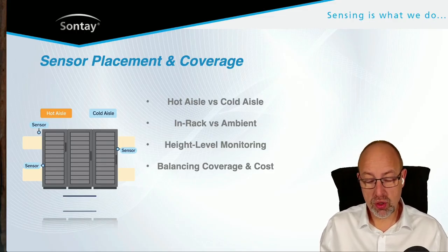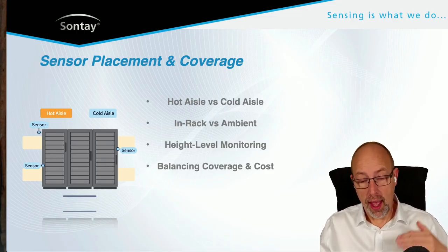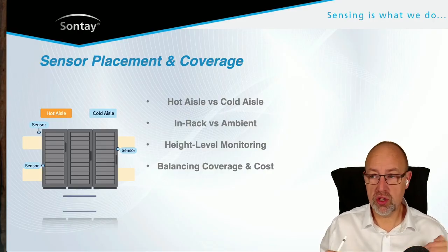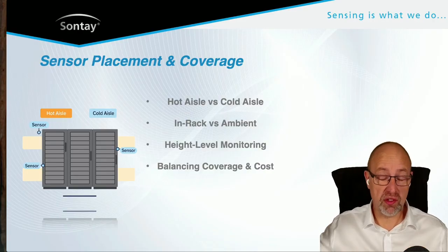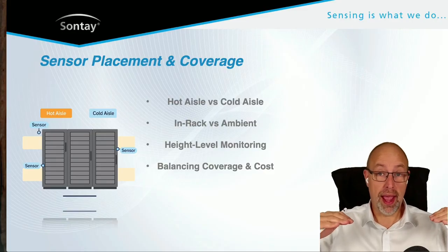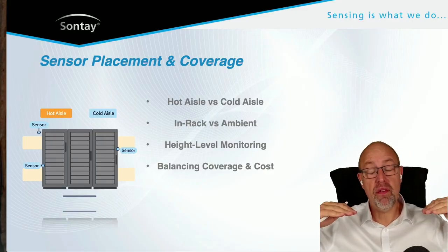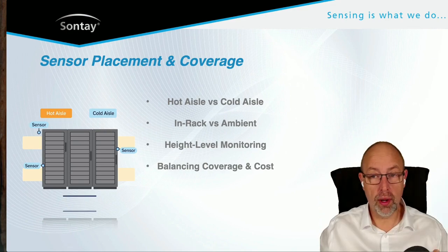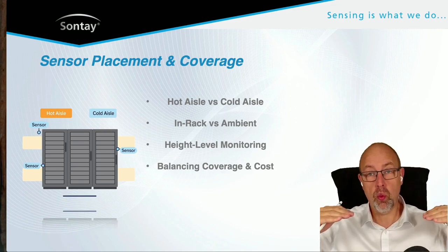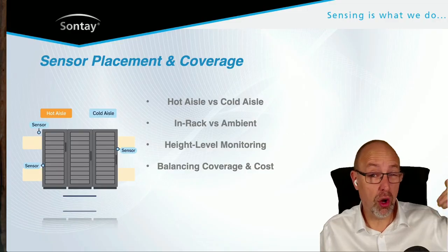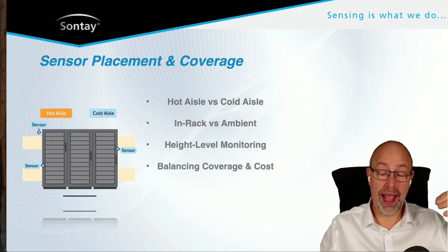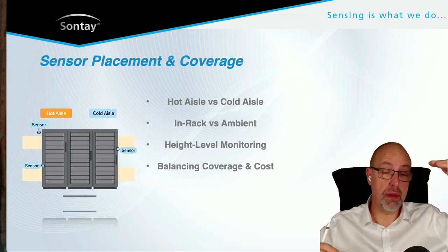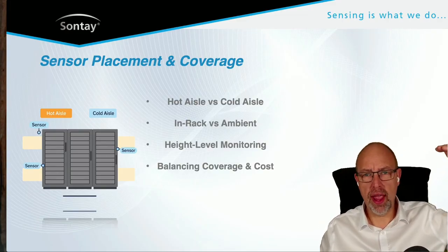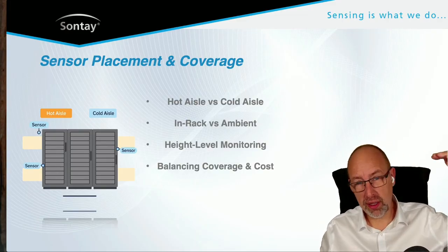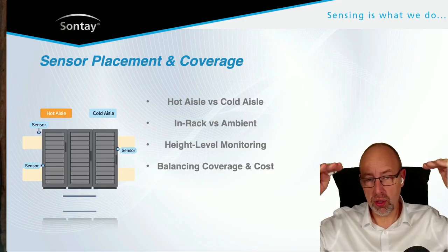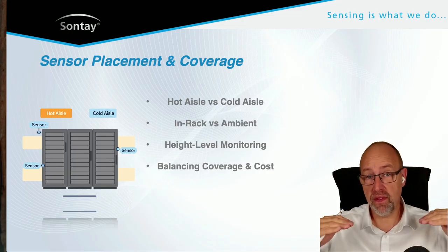Another thing which is quite important is height level monitoring. We have this phenomenon of stratification - hot air rises. Data centers tend to have reasonably high ceilings, so you've got warm air at the top and cool air at the bottom. You need to understand what that stratification effect is, particularly with high ceilings, so you can manage the system. It may be that you've got quite a lot of hot air at high level, but it's not affecting your racks, so you can actually reduce your cooling because you know the stratification effect across your data hall.